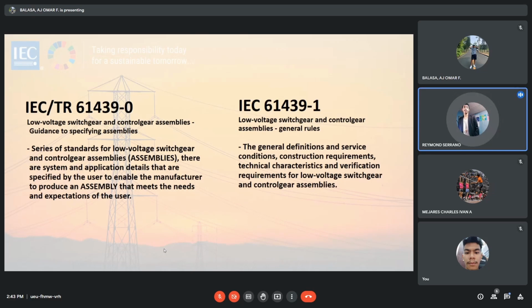So, next is IEC TR 61439 Part 0. Low voltage switchgear and control gear assemblies, guidance to specifying assemblies. Series of standards for low voltage switchgear and control gear assemblies. Assemblies have system and application details that are specified by the user to enable the manufacturer to produce an assembly that meets the needs and expectations of the user.